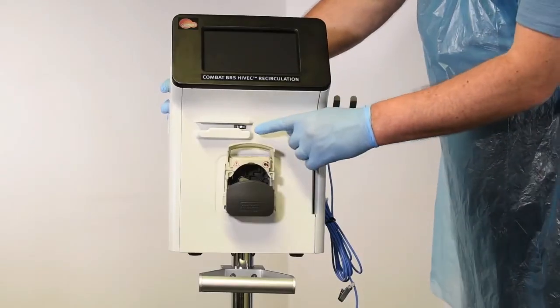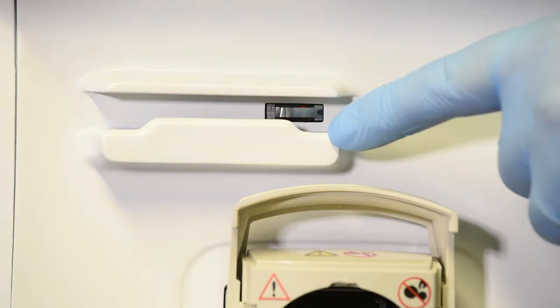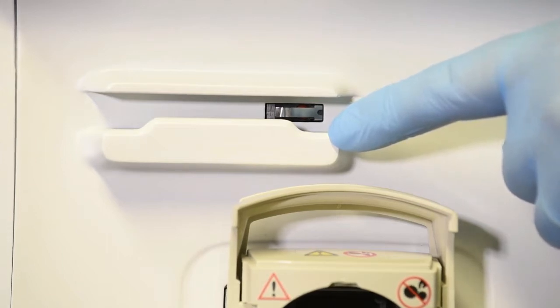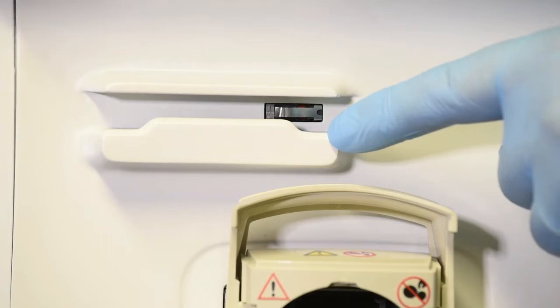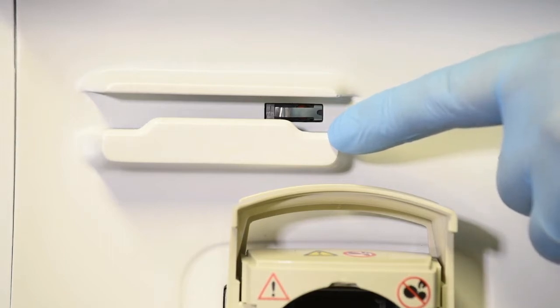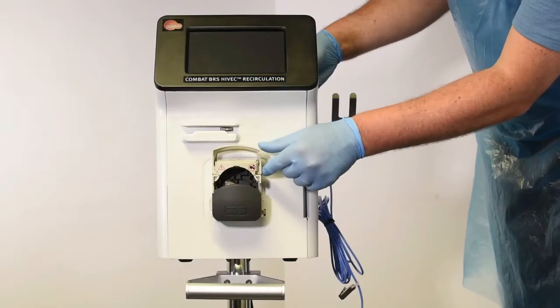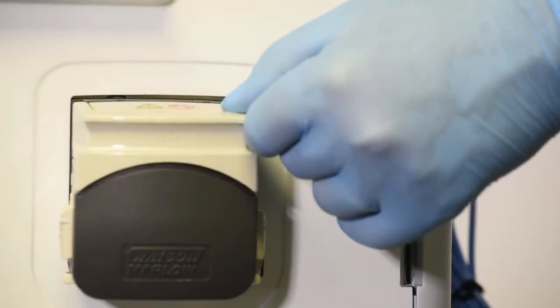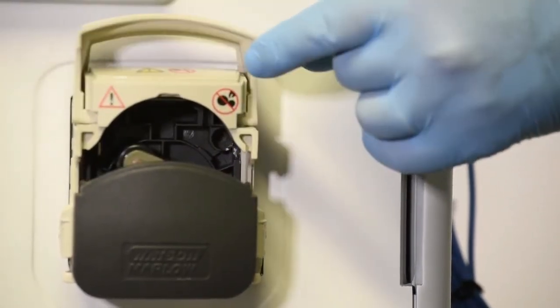The pressure sensor and tube detection. This ensures correct setup and use of the disposable set. The pressure sensor detects overpressure situations with automated cutoff to ensure patient safety and comfort. The peristaltic pump maintains an accurate and continuous flow and recirculation rates.